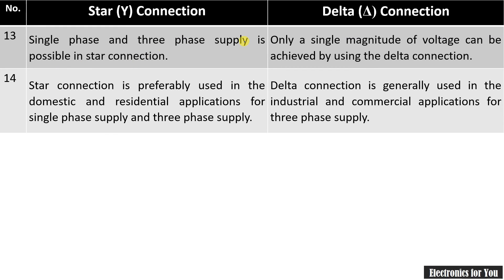Both single-phase and three-phase supply are possible in case of star connection. We can obtain single phase from a phase wire and the neutral wire, and three-phase supply is also possible. Whereas in case of delta connection, only three-phase voltage is possible because there is no neutral wire.